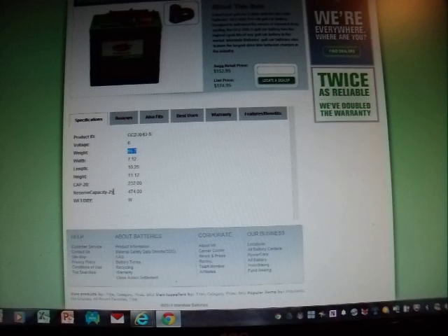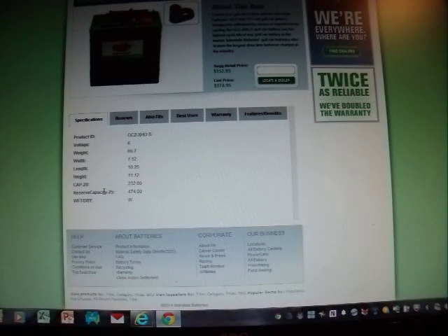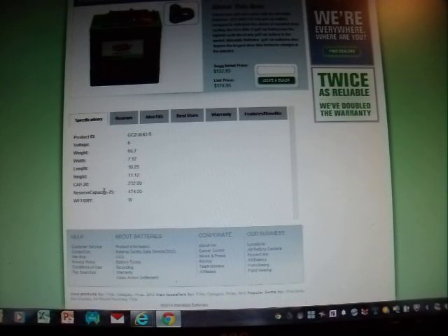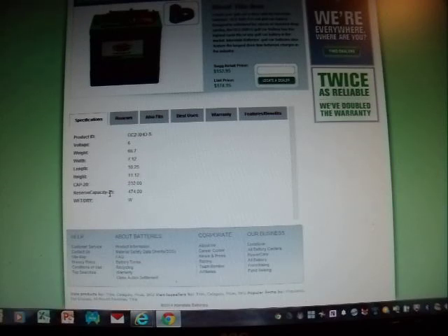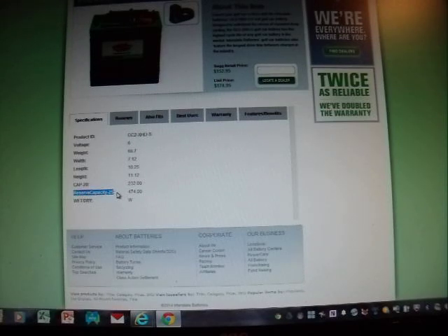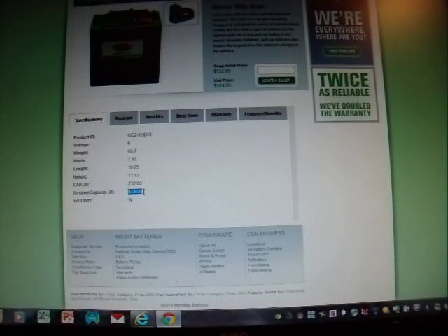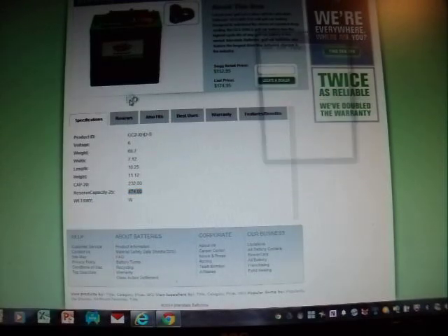The capacity at 20 hours is 232 amps, and the reserve capacity of 25, meaning drawing... what reserve capacity is, is how much or how long will the battery last at a given continuous load. So in this case, when you see that dash 25, that means they are putting a 25 amp draw on this battery, and at a 25 amp draw, it will last you 474 minutes.